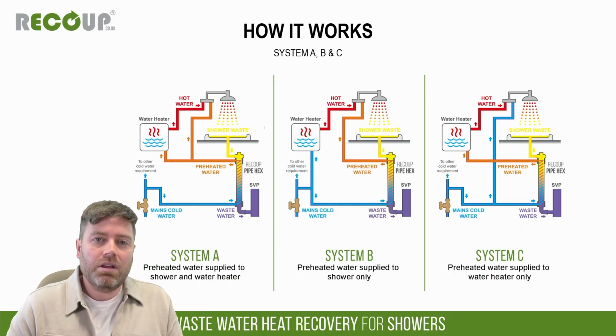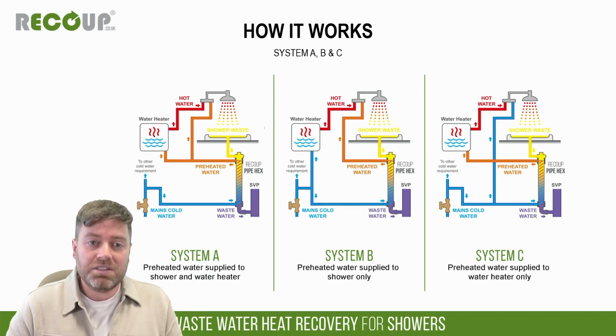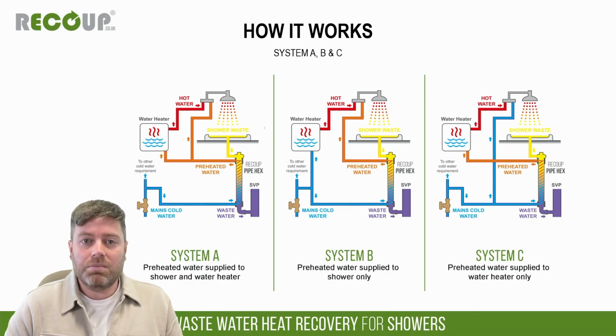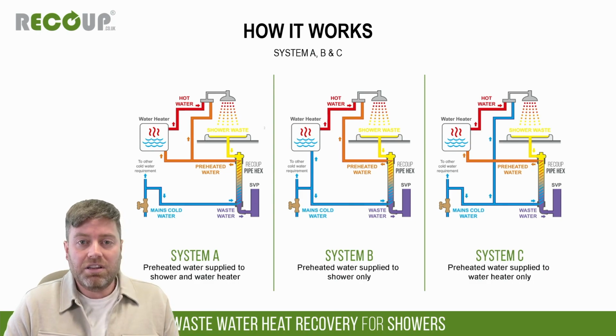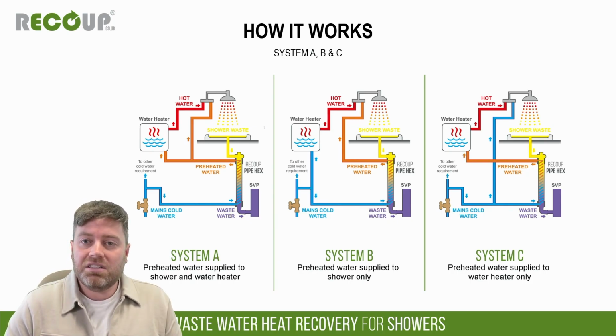Just to recap on those: System A, System B, and System C. System A, you send the preheated water to your hot water source and your shower, most efficient. System B, you send it to the shower only, so applicable for centralized hot water, or for where you've got a system A already in the building. You can only have one system A, so any secondary would be a system B. And then system C, as I say, you don't see so often, where you're just sending the hot water to your hot water source.